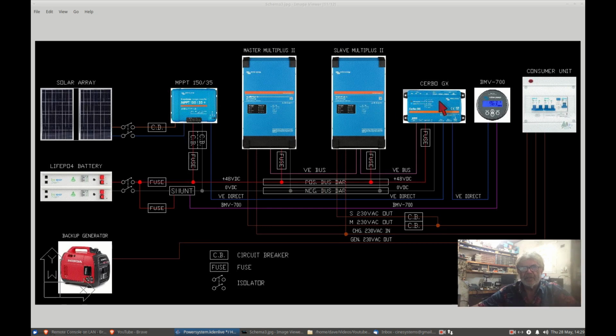So over here on the right hand side we have the Cerbo GX. That's kind of the brains of the system. That connects the data from the MPPT, the 2 inverters and the battery monitor, BMV 700, together, and also provides online monitoring. So I can actually log on to the internet or my network and see what's going on with the power system. BMV 700, that gets its information from the power shunt and the positive feed. So it looks at the voltage and the current going through from or to the battery, and it will give us a state of charge, power in, power out, whatever. So a good thing to have.